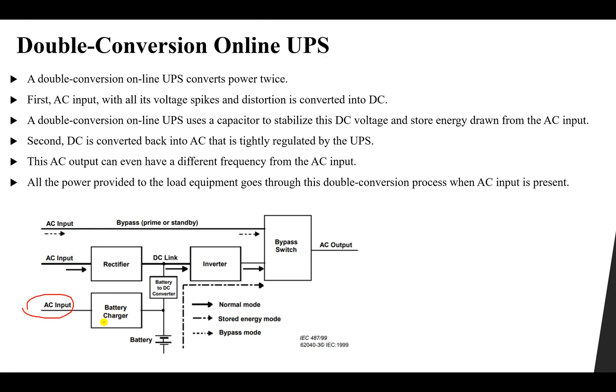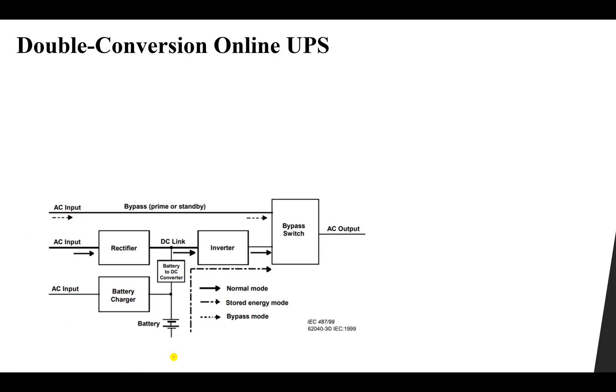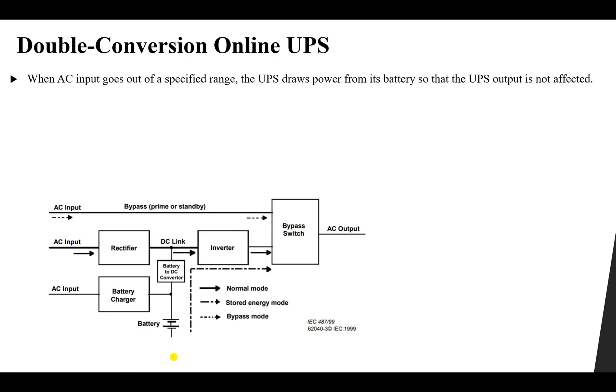We also have a battery charger that takes the AC input and charges the batteries, storing energy for when the AC input goes off or has a problem. This is why the third mode is called the stored energy mode. When the AC input goes outside a specified range, the UPS takes electrical power from the batteries — DC power goes from the battery through the inverter to the AC output.